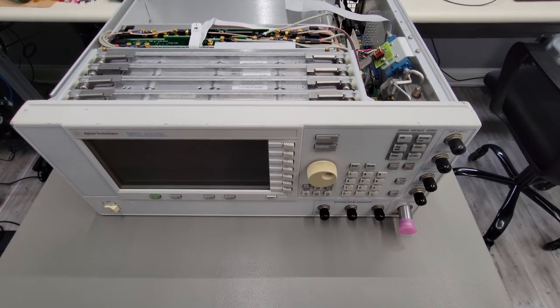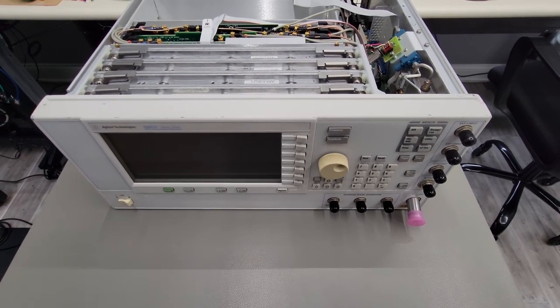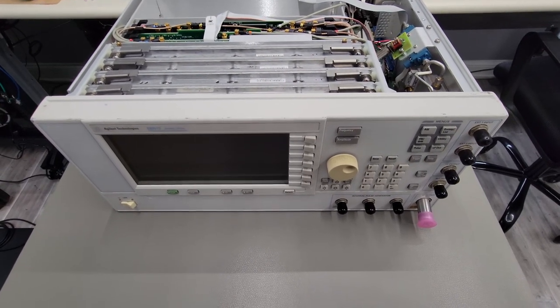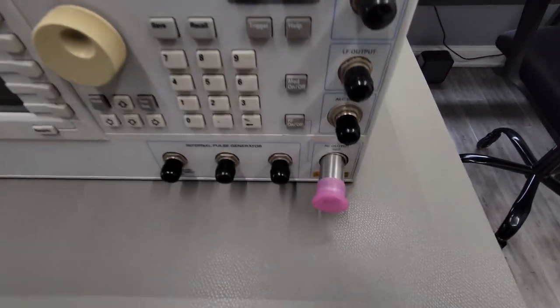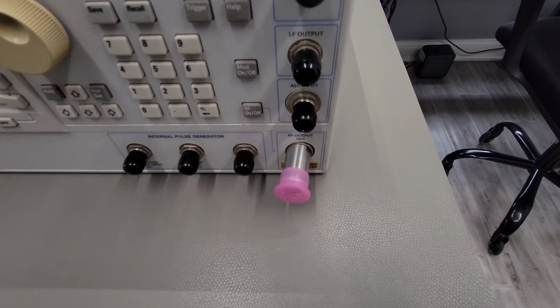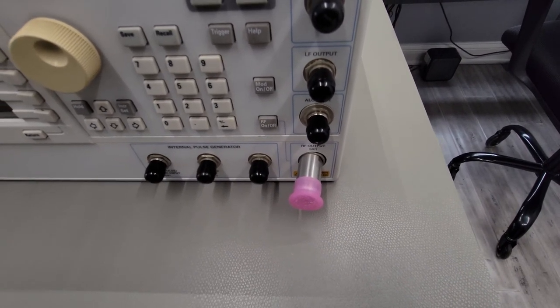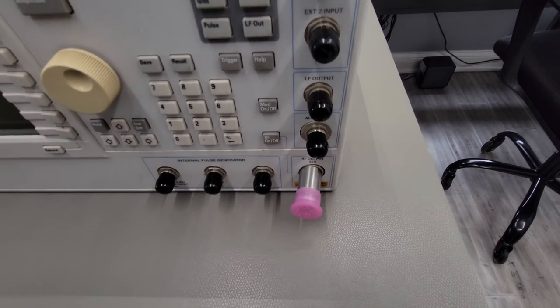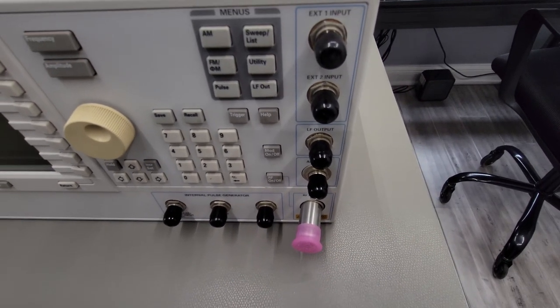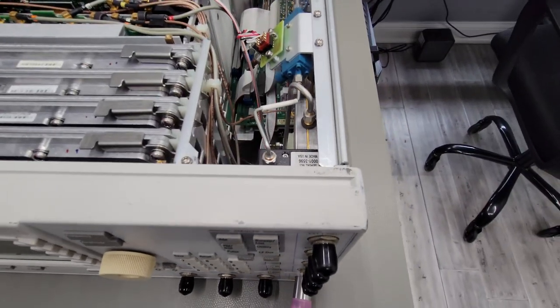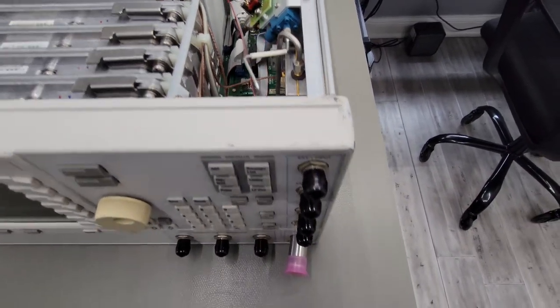So in order to begin troubleshooting this unit, the first thing I'm going to do is drop the front panel. And that's going to be a little tricky with this bent output connector, but this is also the reason I'm doing it, because I want to make sure that this connector is not damaged on the inside, where it does connect to the semi-rigid coax for the rest of the instrument.